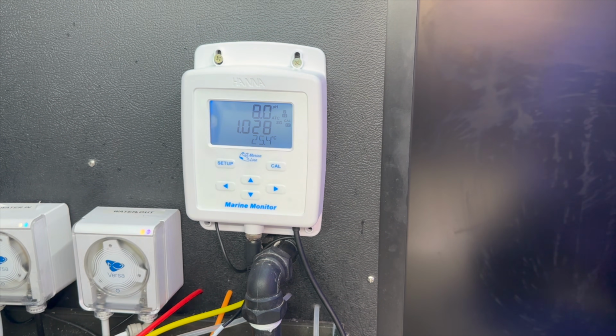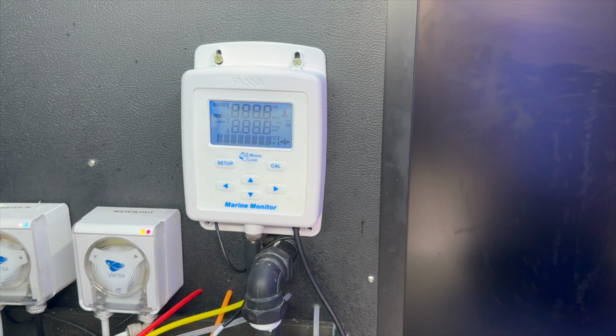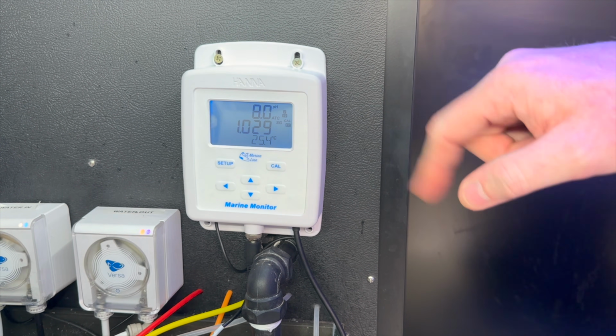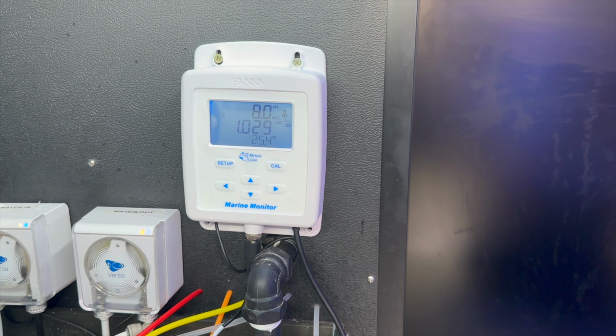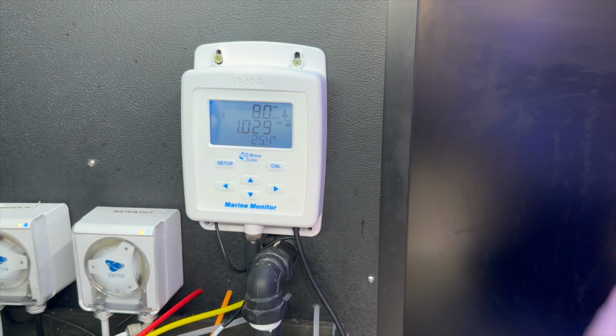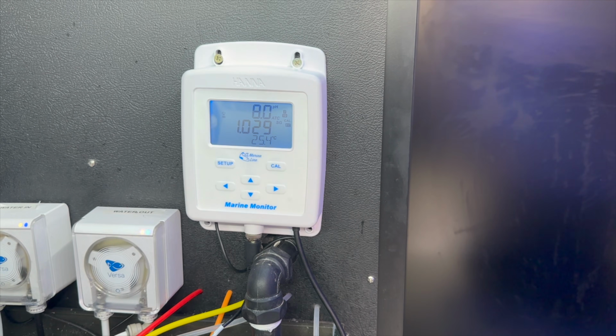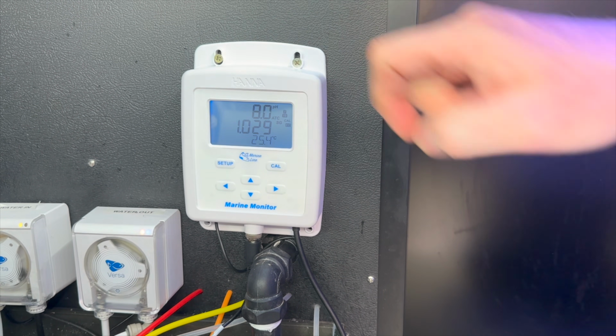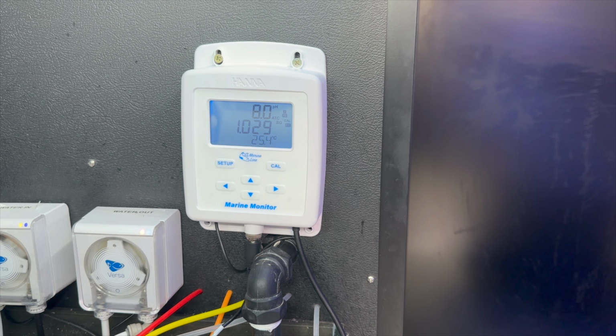But if I disconnect the factory power supply and I hook up my own high quality power supply, let's just give it a second to boot back up. And we'll see where the specific gravity reads. It starts off high, comes down, you can see the little hourglass flashing. We get to 1.029, which is where I measure the specific gravity of this tank with my digital refractometer from Milwaukee. It thinks for a second and then that hourglass will go away. Already has, it's happy with the results.